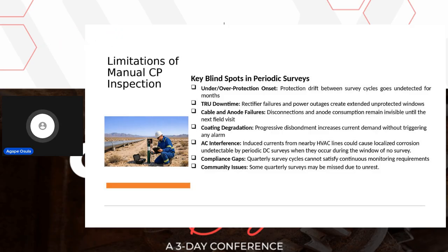Now, sometimes you also have TRU downtime, right? This is very popular in Nigeria. There are specific issues that could take your TRU out of service. Now, if you are going to depend on your next CIPS survey to know that the TRU is not delivering current to your system, particularly for impressed current systems, right? If you're doing this every 2 years and you wait till that time, that means for the next 2 years, you will not know that something is happening on that line.